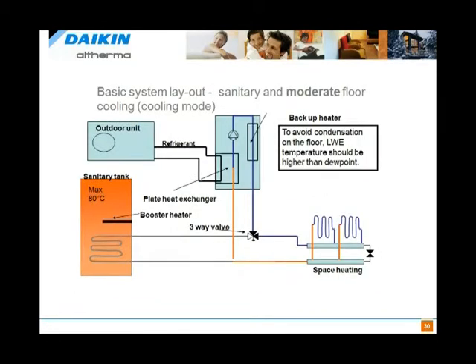And pretend this is heating only. This is the only slide I had, but what I want to do is demonstrate the three-way. This is a 3-way valve with an indirect water heater in a priority domestic hot water setting going out to space heating. Now that space heating could be radiant, it could be convectors, it could be low temperature baseboard, which we're bringing in, which you may find attractive, as well as radiators and air handlers. And it's something you should be very familiar with.